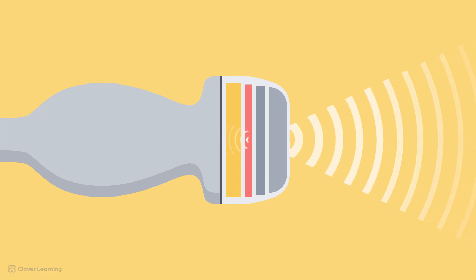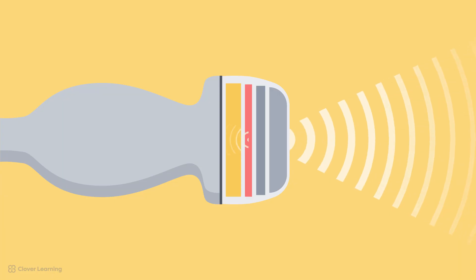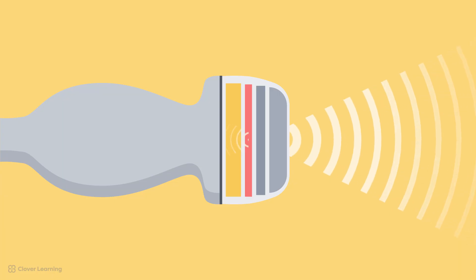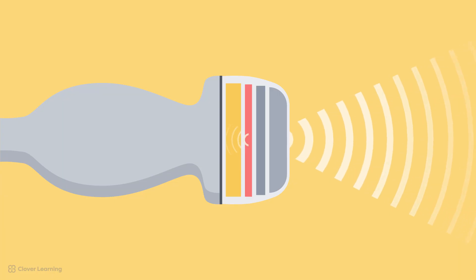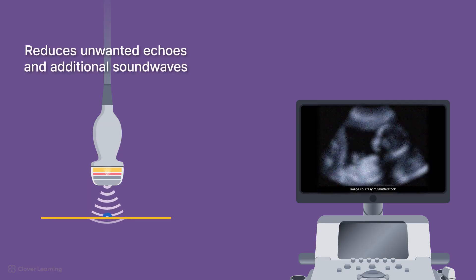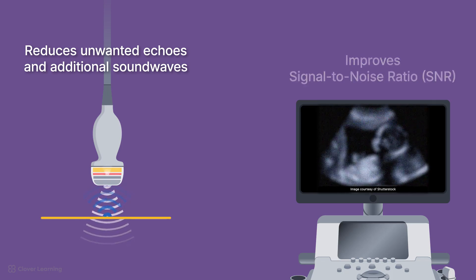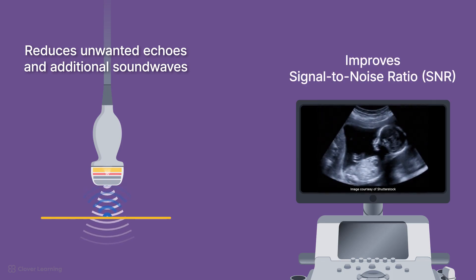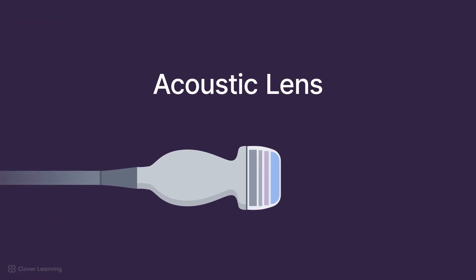Ringing effects and their relationship to the quality factor, or QF, will be discussed in another lesson. By absorbing the excess mechanical vibrations from the crystal immediately, it reduces unwanted echoes or additional sound waves that overlap with the returning echoes, which improves the signal-to-noise ratio, or SNR.